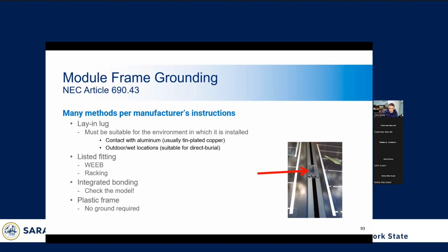And so, if there is no path throughout the system, it can cause an overcurrent protection device or the pathway for fault current to not trigger the fault detection equipment. And then it can cause someone to be electrocuted or cause someone to die. Again, here we see the integrated mid clamp that provides the bonding of all the modules. And there are other ways to do it too. We'll see a few of them throughout the next few slides.